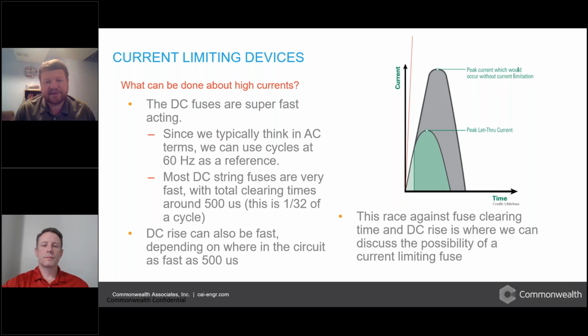Now, if you look closely at this graphic, you'll see there's a red line running very close to the current y-axis. That is more indicative of what a DC circuit rise is going to look like compared to an AC waveform rise. So just to give you a visual on how much faster a DC circuit is going to rise to its prospective fault current, it can be much, much faster than a typical AC waveform. It's a good graphic to put in perspective the differences of what we're talking about.